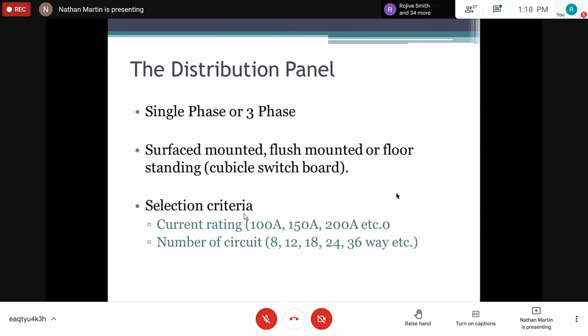Now, your panels can either be supplied as a single-phase panel or a three-phase panel. What's the difference? We know that in a single-phase system, what we have learned so far from year one coming up, right, is that a three-phase system has three live wires, right? It might be a three-wire system, and a four-wire system will have three phases and a neutral, right? In a single-phase system, for our distribution network, we would have two lives, right, two phases, and a neutral, right, a three-wire system. So this is basically how the panels are designed.